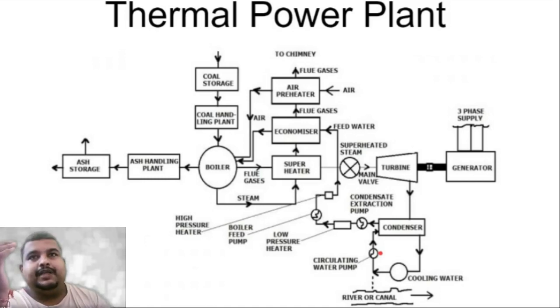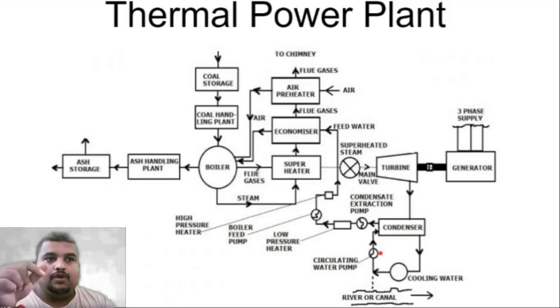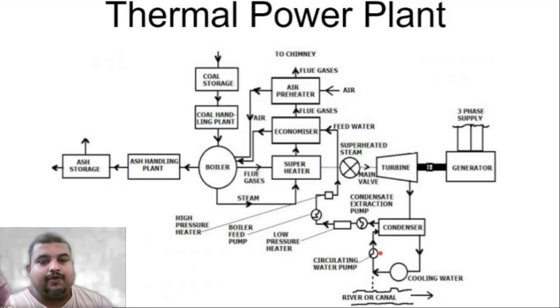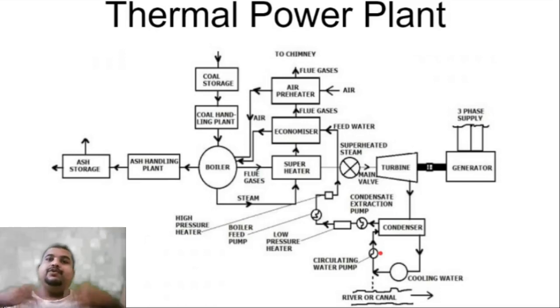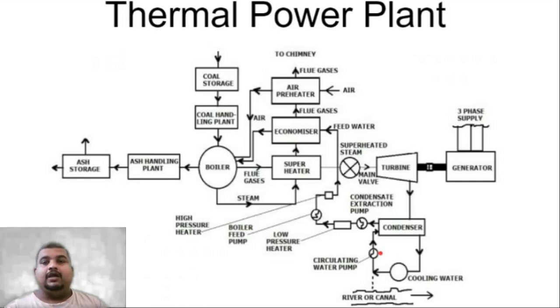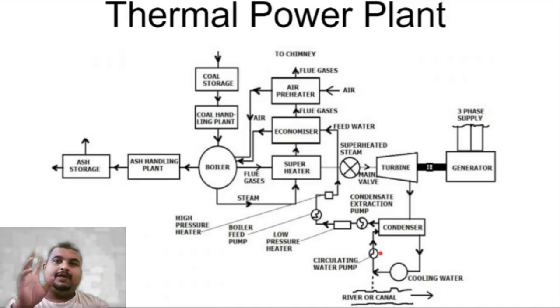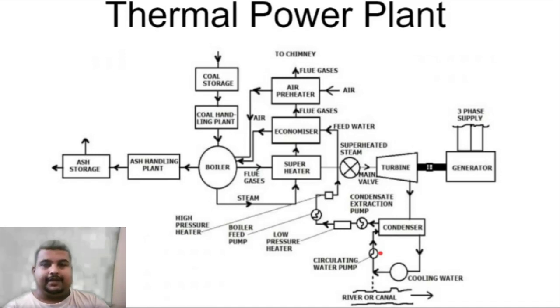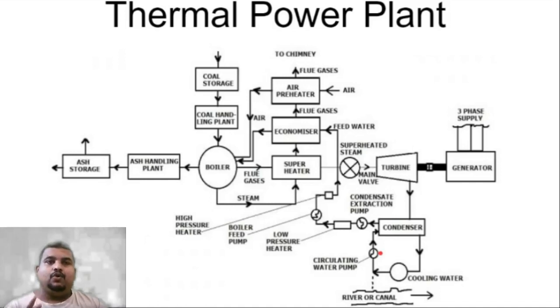When the coal bunkers provide coal to the coal mill, the coal mill crushes it into powder form. Why is coal crushed into powder — pulverized form? So that the surface area of the coal increases. Because of this increased surface area, burning is easier and the efficiency of burning is increased. If there is residue left after burning, it means the burning process was not proper — we don't want to waste even part of the coal that we have purchased, which is why we increase the surface area.